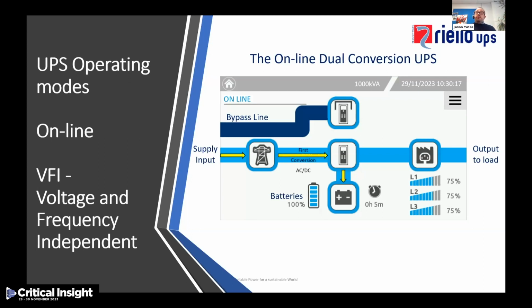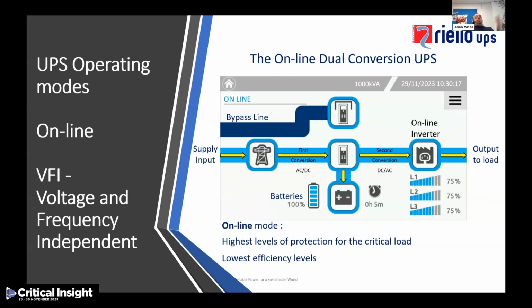Basically, we take the main supply that comes in and convert that AC into DC. That represents our first conversion. Then we take that DC and reinvert it, so we recreate the AC waveform from DC back to AC again. The system is referred to as online because the inverter is permanently supplying the power to the critical load. The reason we do this is that all of the nastiness of the incoming main supply gets filtered out and we produce a completely clean waveform for the critical load. Unfortunately, the online dual conversion UPS system, although it provides the very highest levels of protection for the critical load, also produces the lowest efficiency levels in terms of operating modes, because of the conversions within the UPS system.